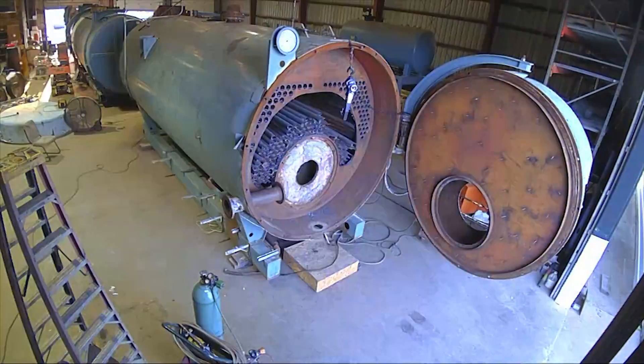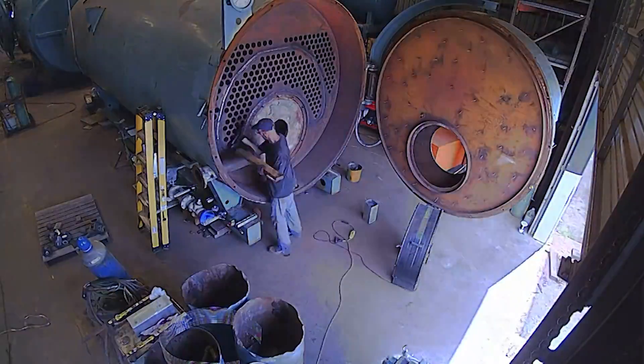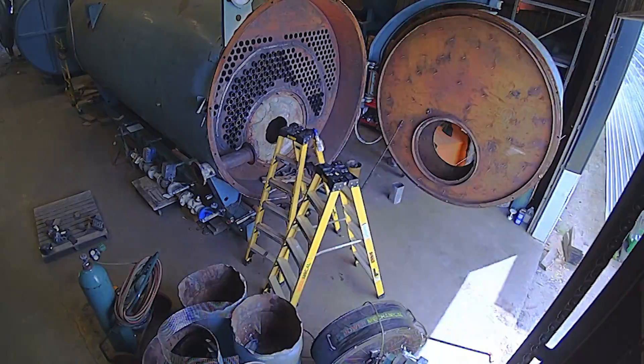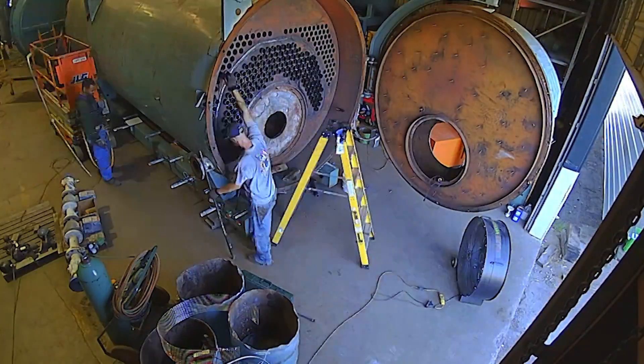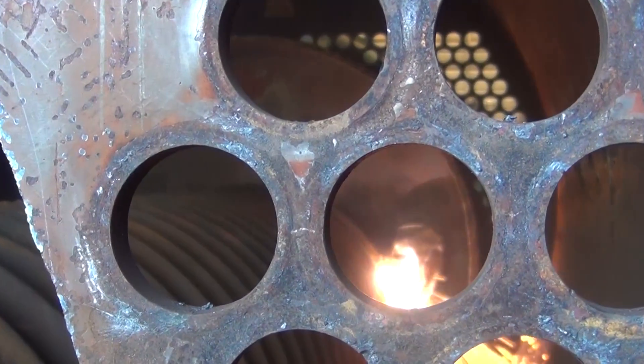In this video, you will see the team at Power Mechanical restore a 1993 Cleaver-Brooks 600-horsepower fire tube boiler by replacing the tubes as well as an interior tube sheet. This three-pass wet-back design has an additional tube sheet within that was no longer satisfactory for the stringent requirements the material needs to meet.